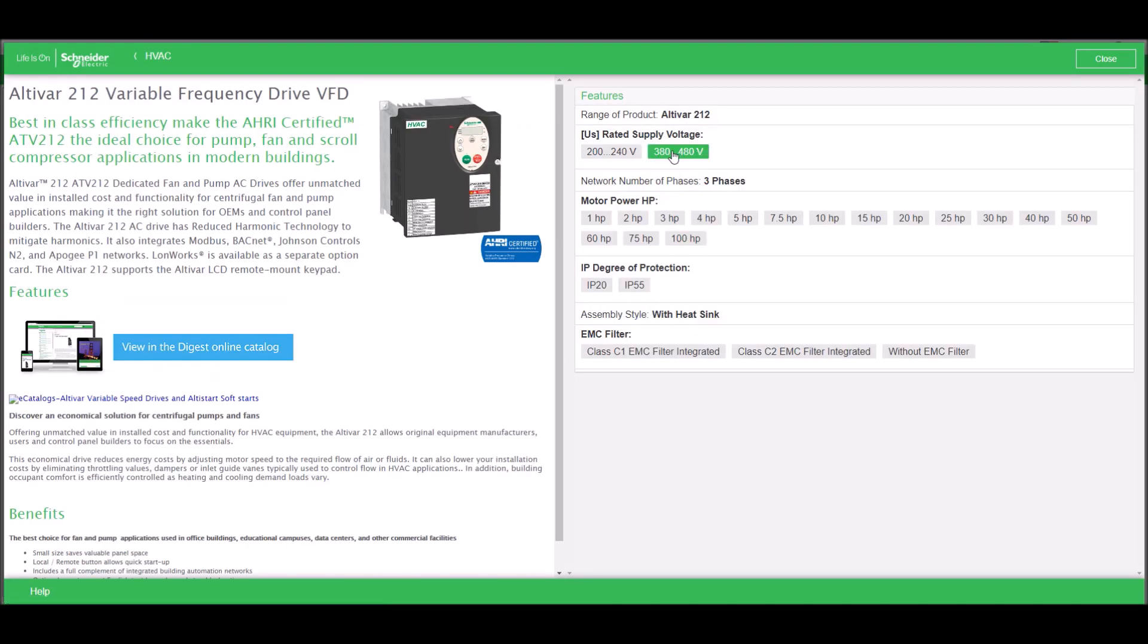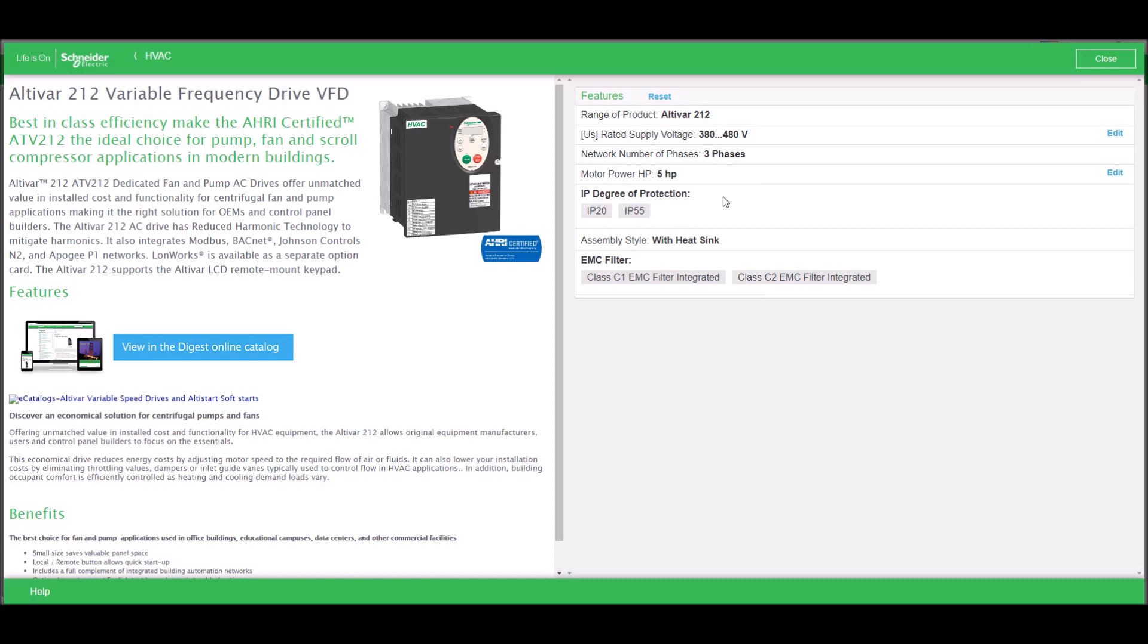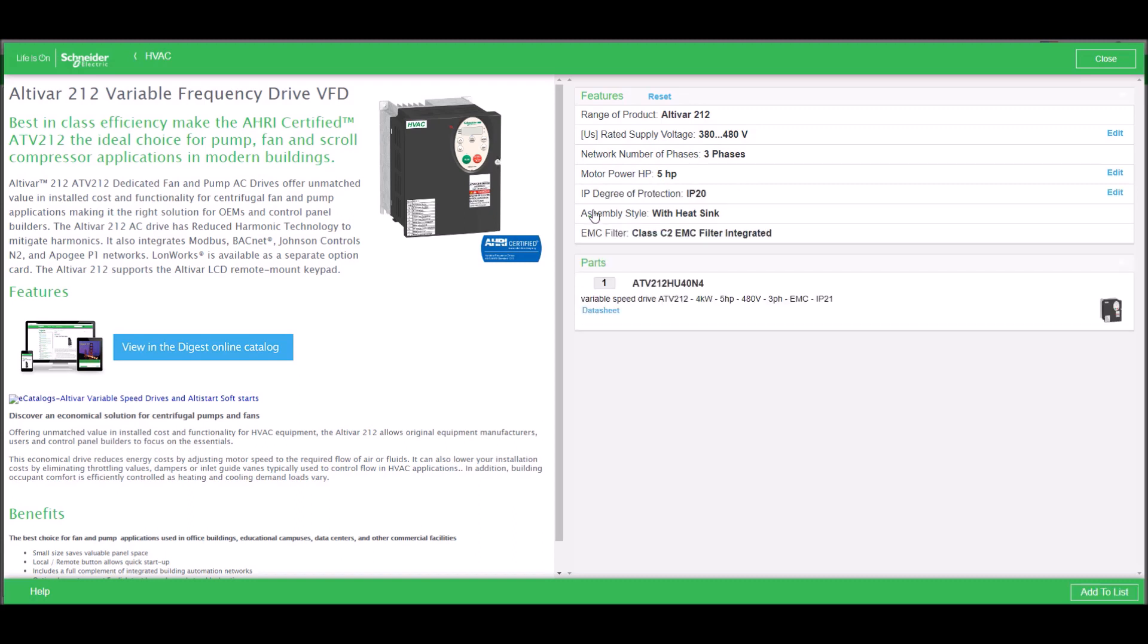It's a 480 volt system, three phase, and the customer wants a 5 horsepower drive, and standard protection, which in this case is IP20. The part number selected is ATV212-HU40N4.